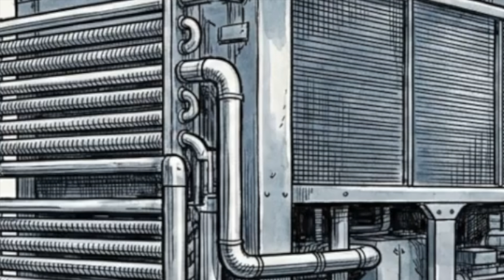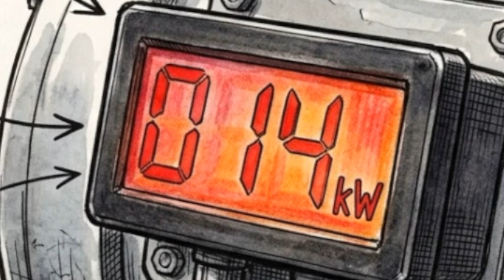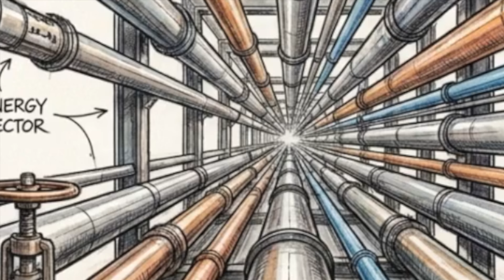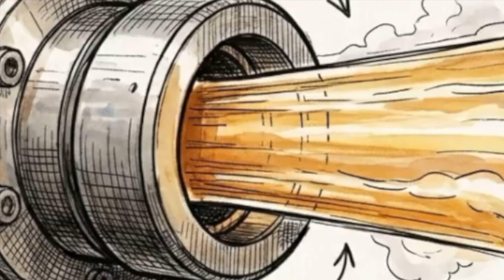There is a secondary physical benefit. Removing this thermal load takes massive pressure off the condenser. The compressor itself requires less electricity to run. By simply intercepting the path of the existing energy, you shatter the double energy penalty. You generate free hot water, you drop the electrical draw.